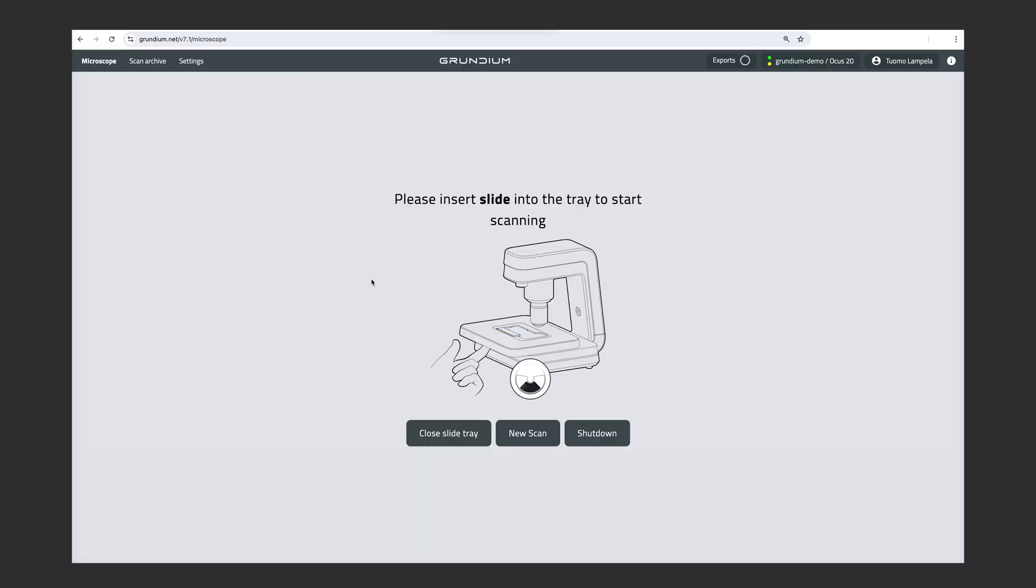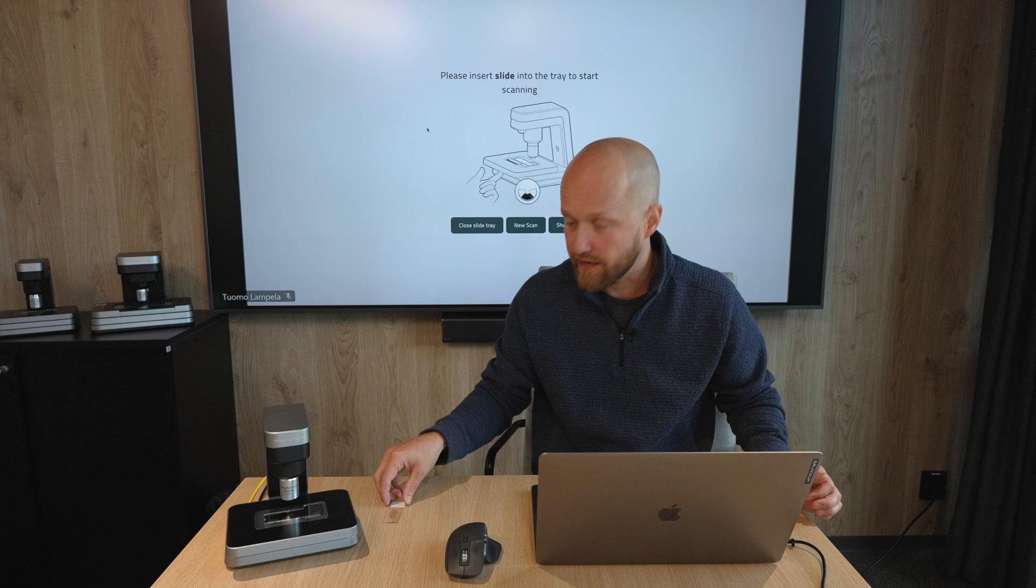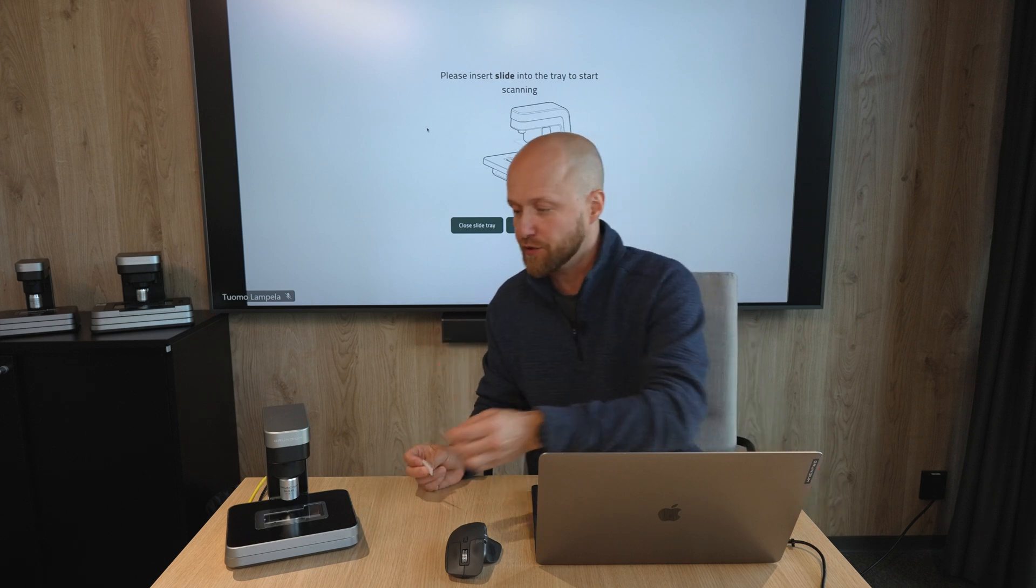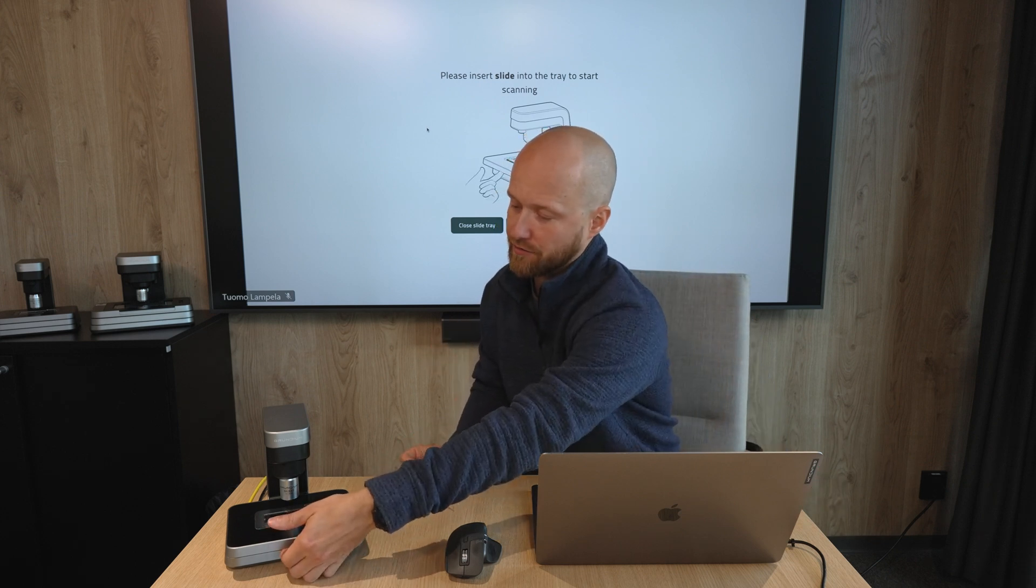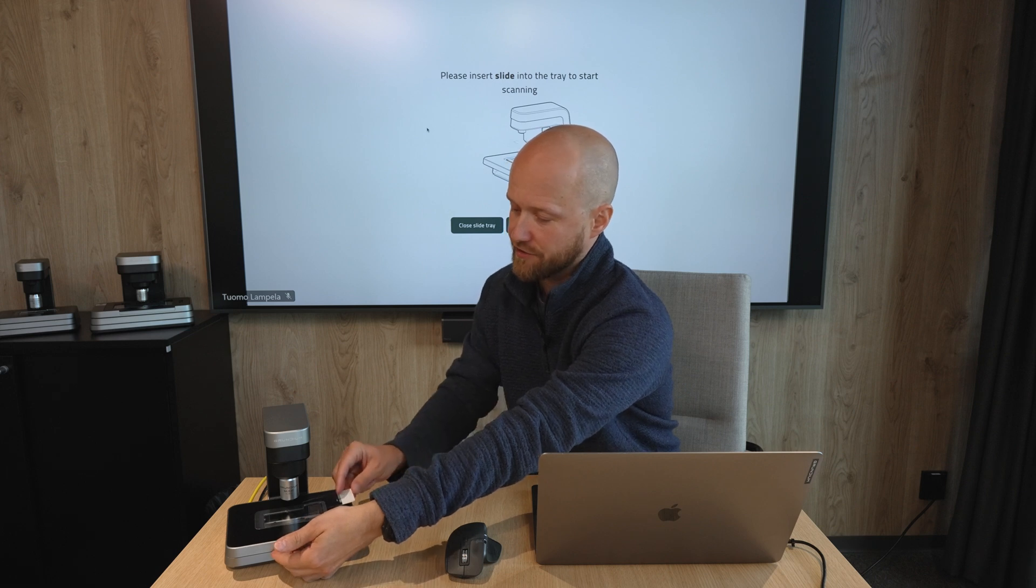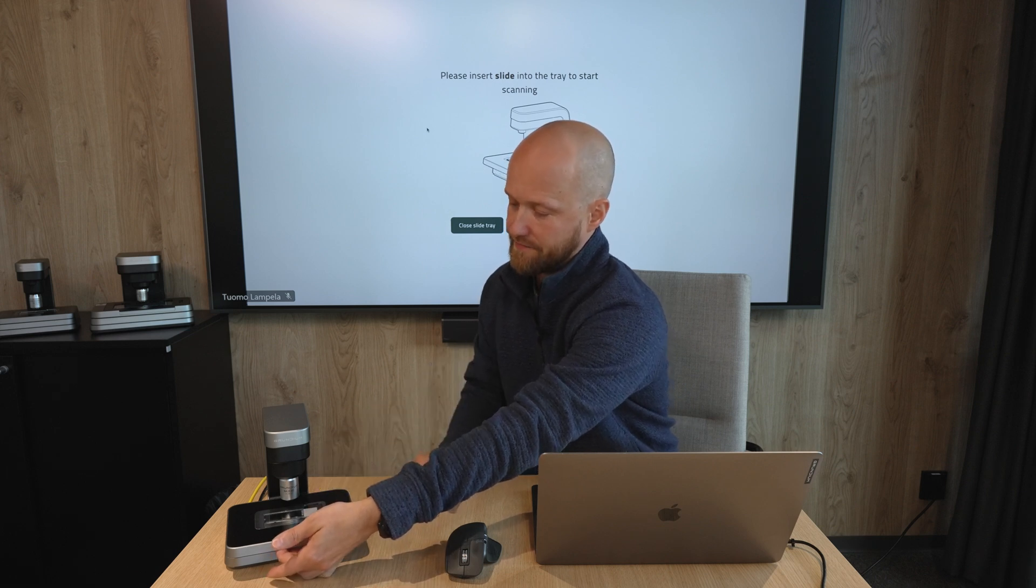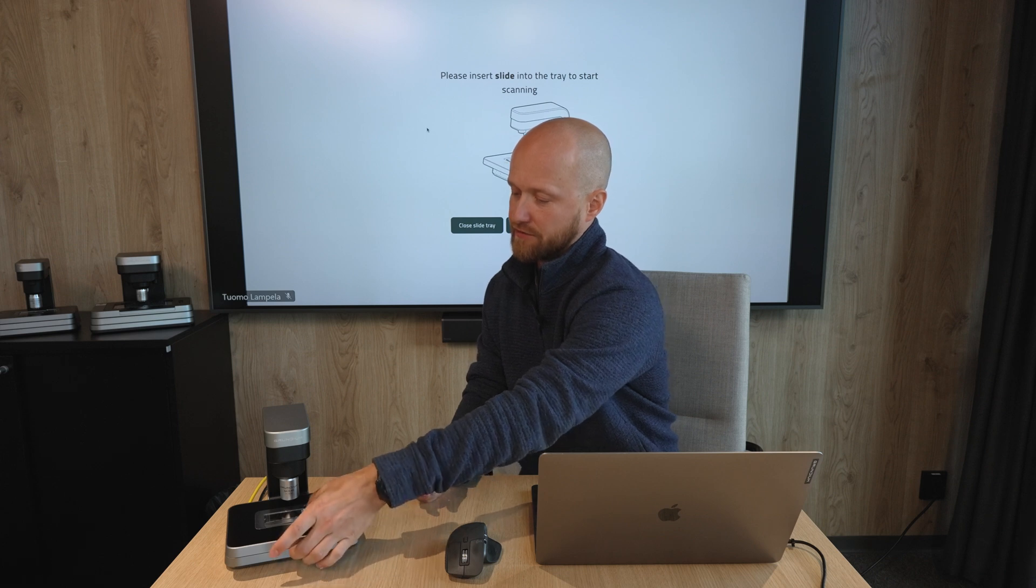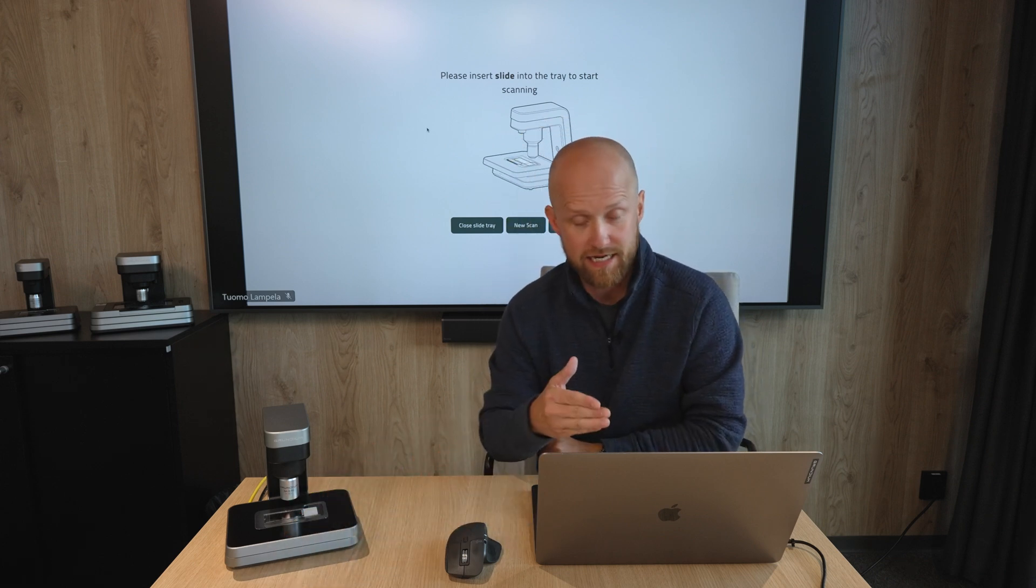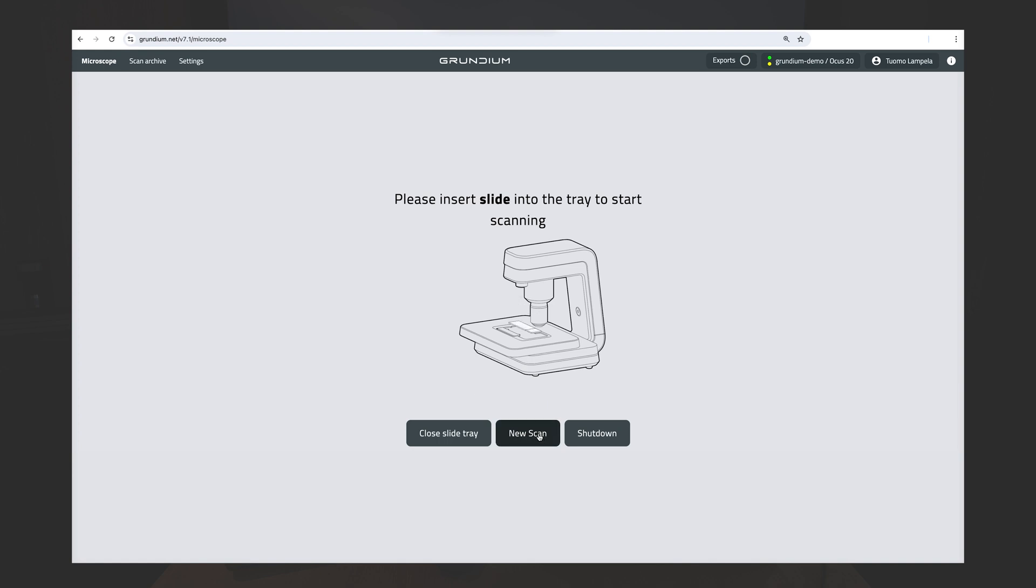And the scanner is telling me to insert the slide. So, I have a slide here, and what I'll do is open the slide holder by moving the latch under the scanner, insert the slide, and then close the latch to secure the slide. And then, in the UI, I'll click on New Scan.